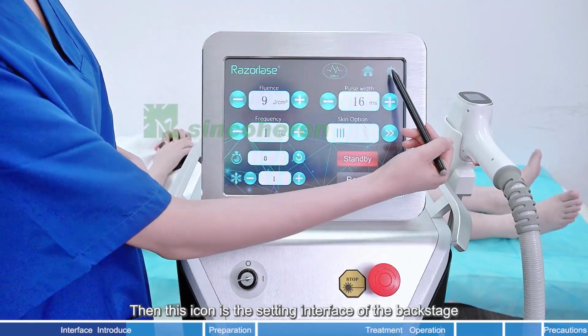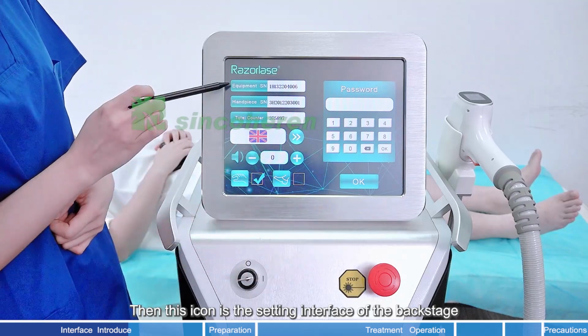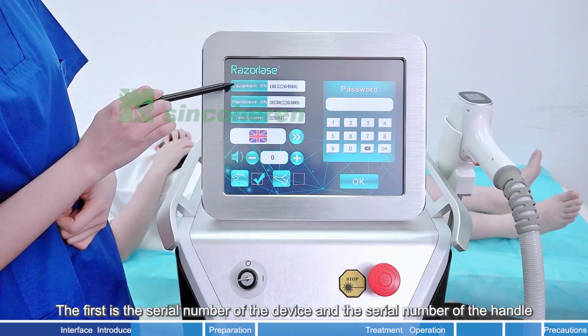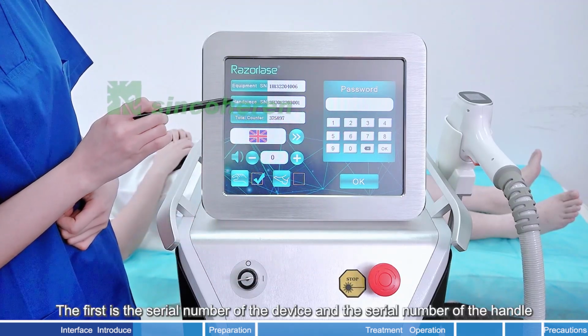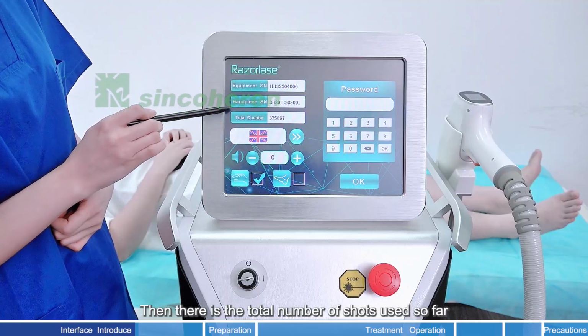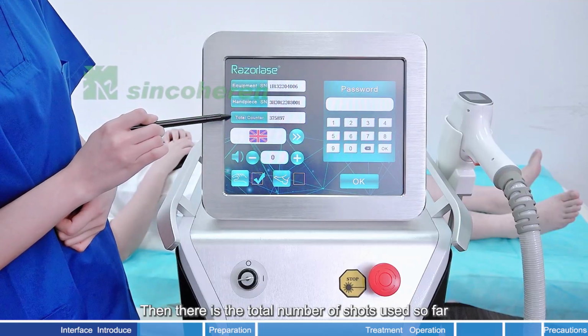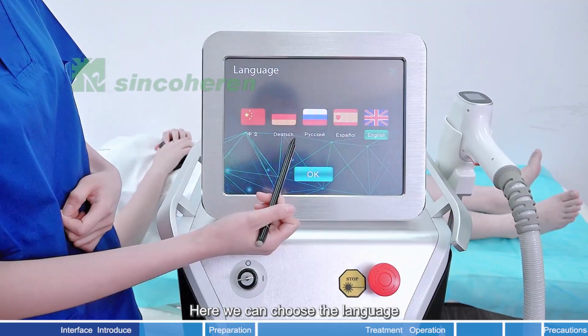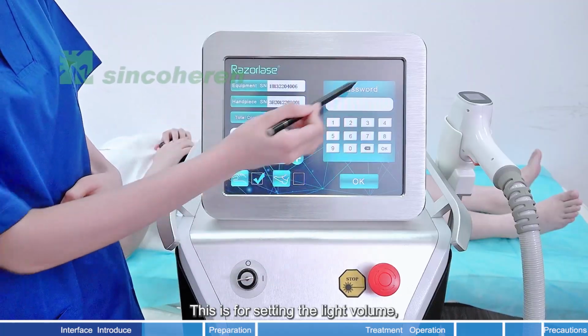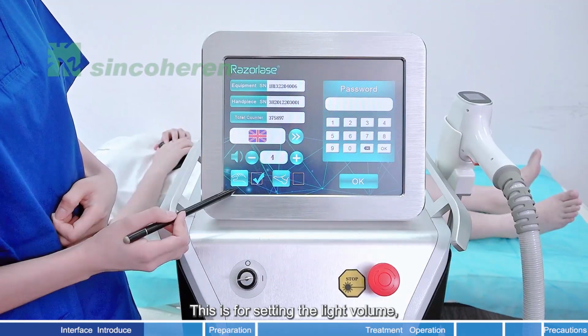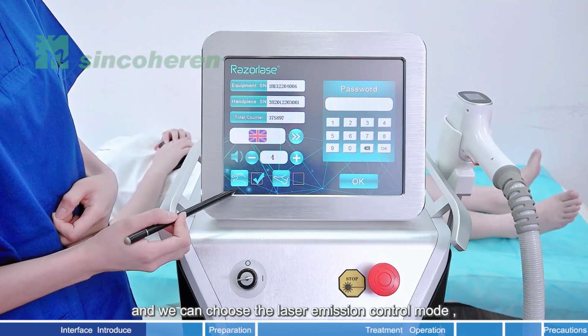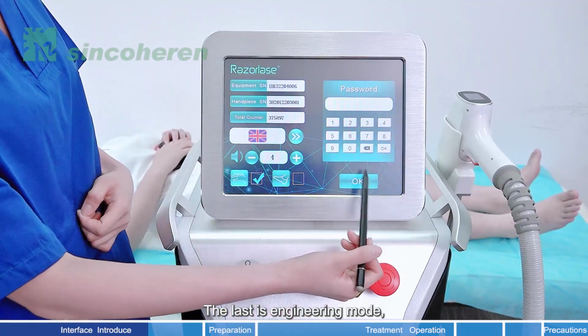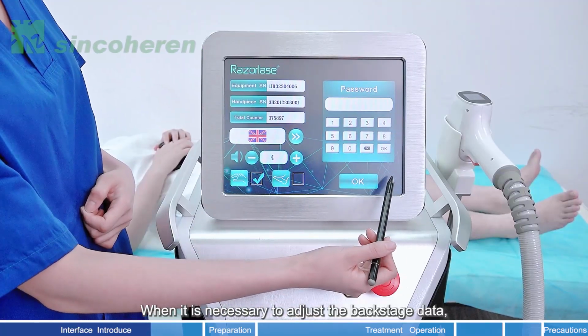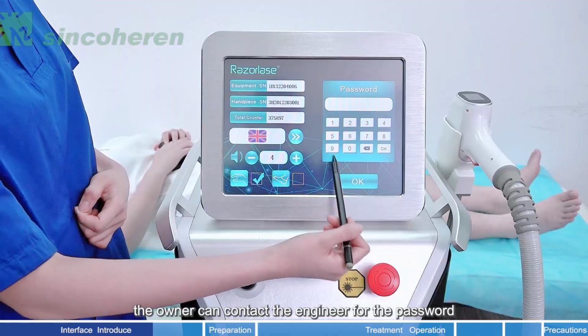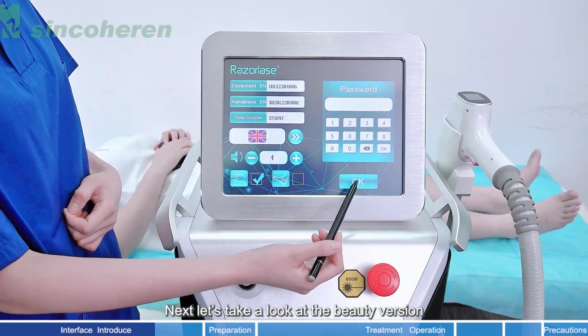Then this icon is the setting interface of the backstage. The first is the serial number of the device, and the serial number of the handle. Then there is the total number of shots used so far. Here we can choose the language. This is for setting the light volume, and we can choose the laser emission control mode. The last is engineering mode. When it is necessary to adjust the backstage data, the owner can contact the engineer for the password.